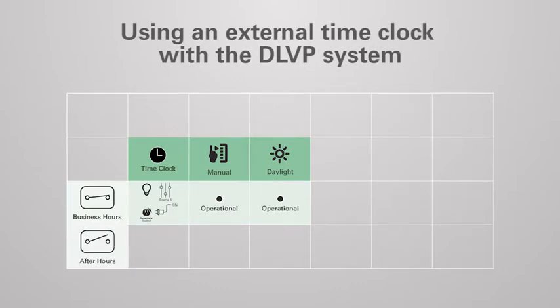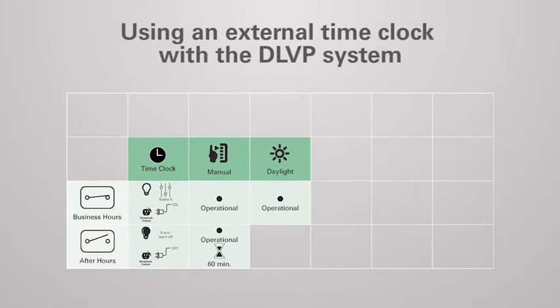When the time clock contact opens and the system enters after hours mode, the lighting will blink warn and begin a five minute off delay. Receptacles will turn off 30 seconds after the lighting. Manual wall station commands from this point forward will begin a one hour countdown timer to ensure that lighting and receptacles are turned off automatically. Daylighting controls will operate if lighting is on and there is adequate natural light in the space.